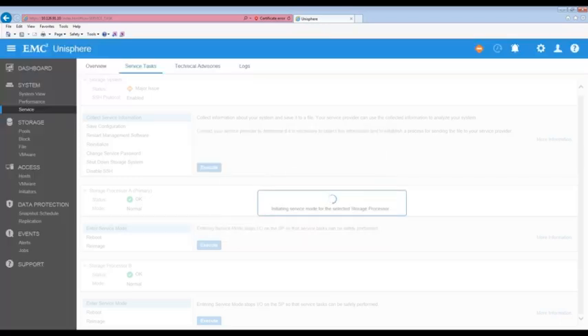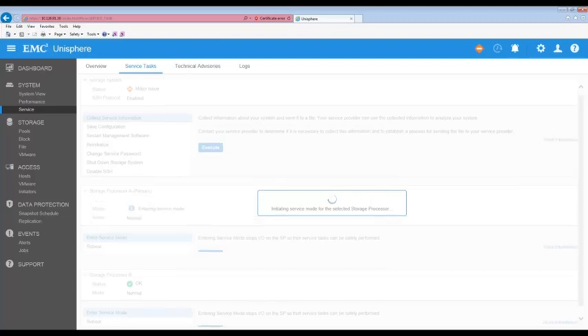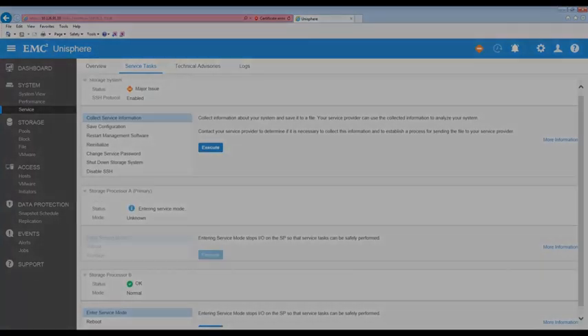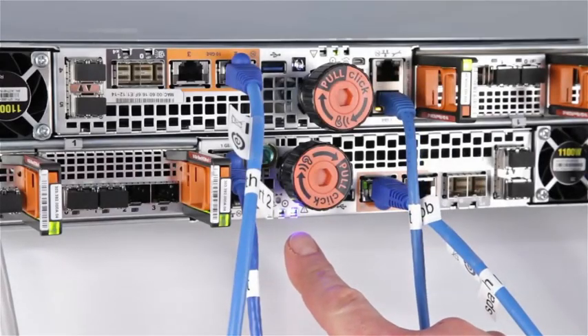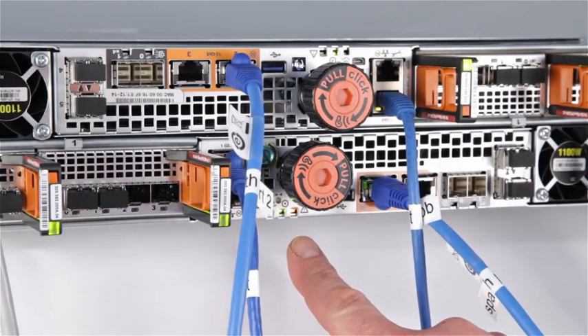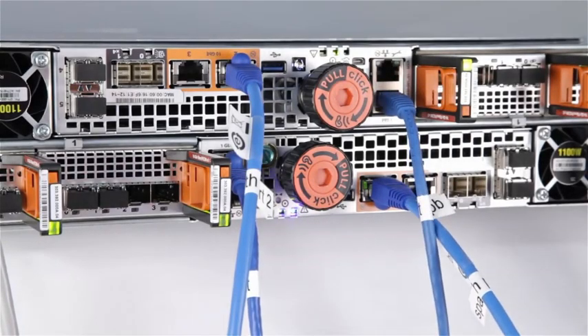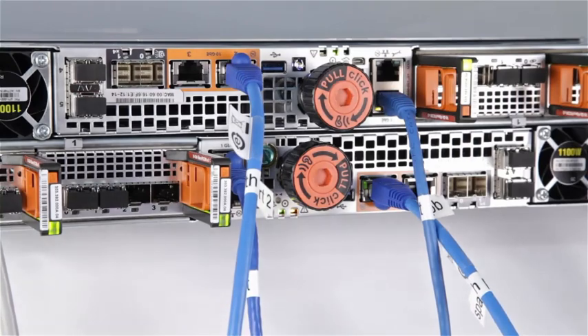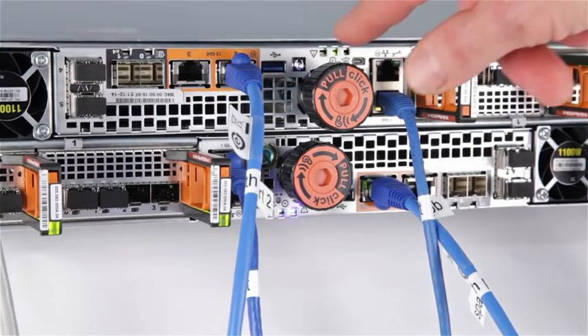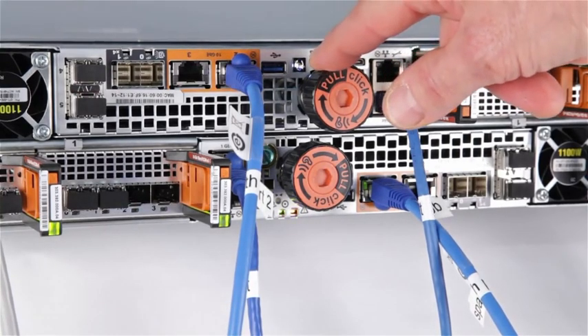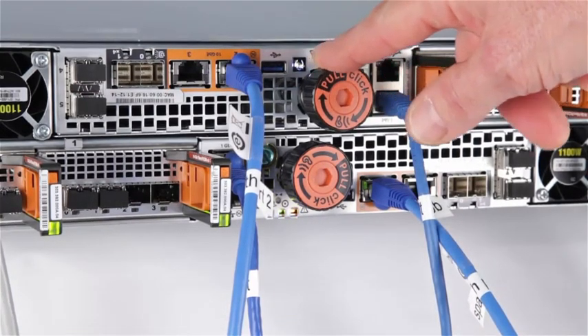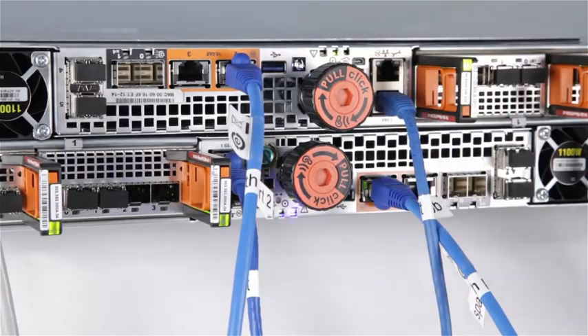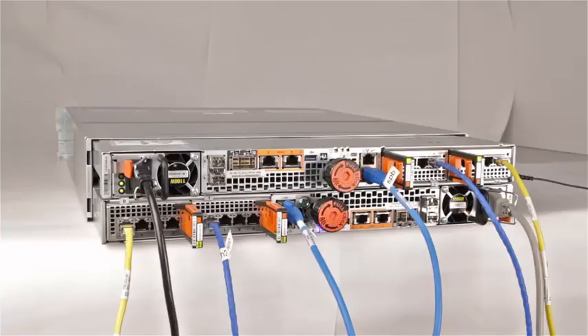Wait until the SP fault light is flashing alternating amber and blue before removing the storage processor. Here we can see that SPA is in Service Mode. Also notice that the unsafe to remove LED is illuminated on SPB. Make sure that you do not remove an SP with the unsafe to remove LED illuminated.